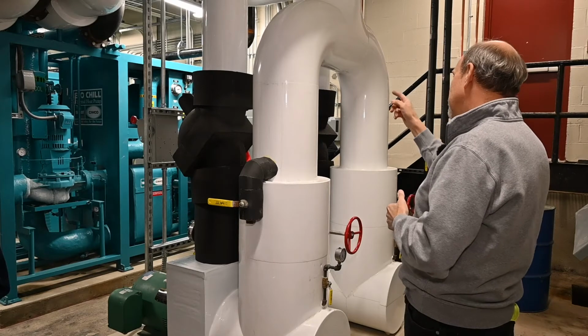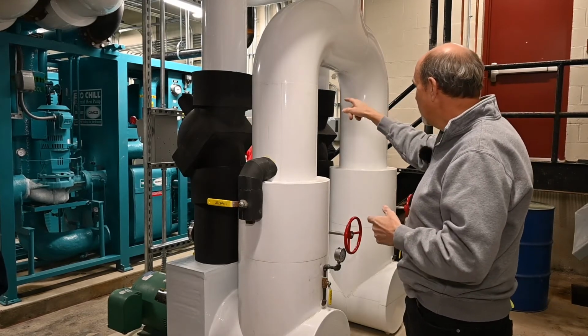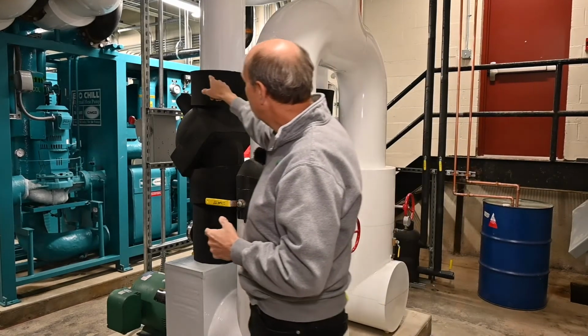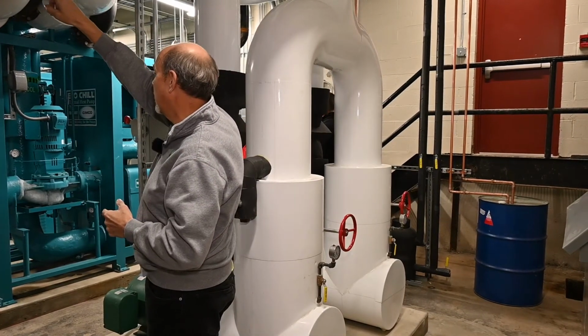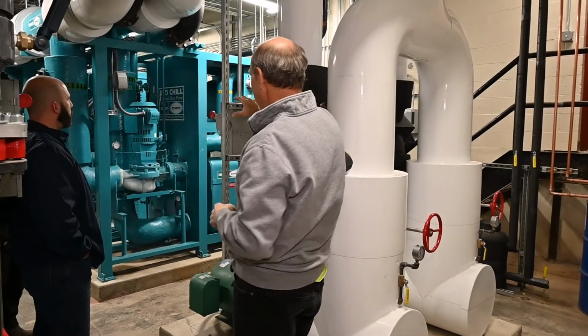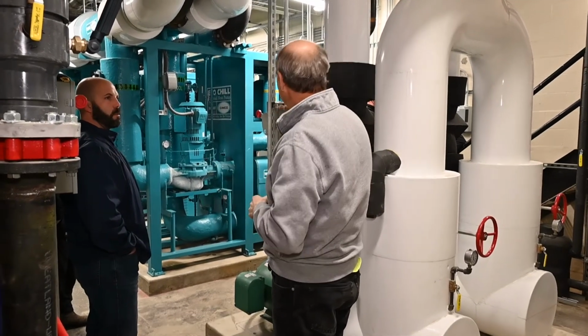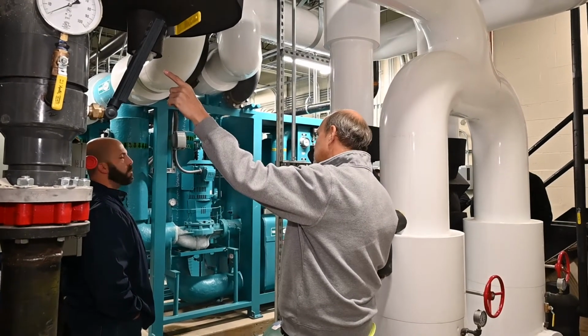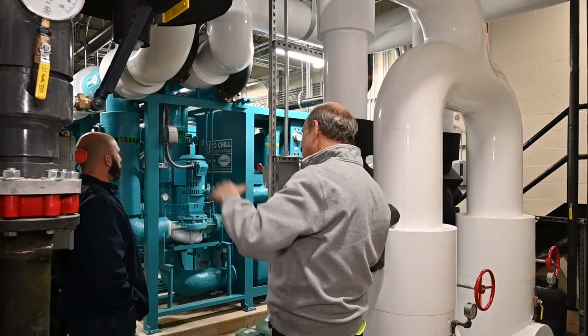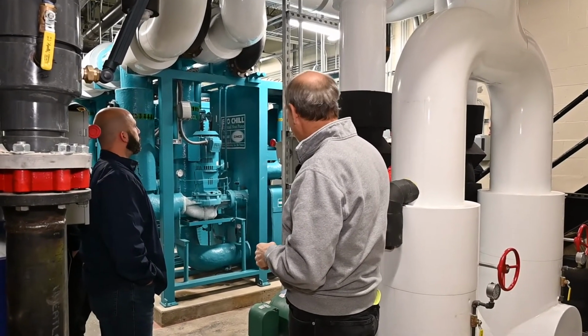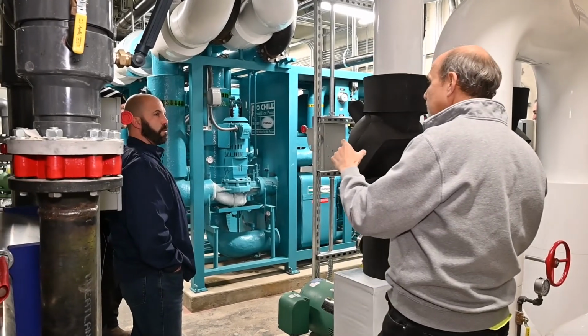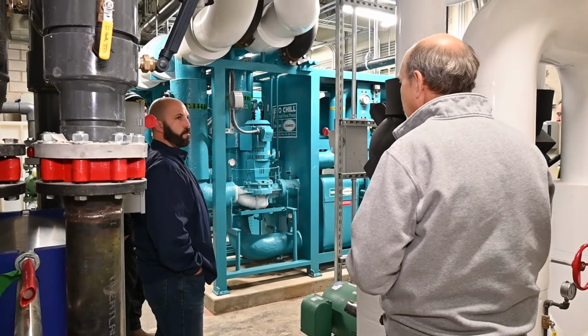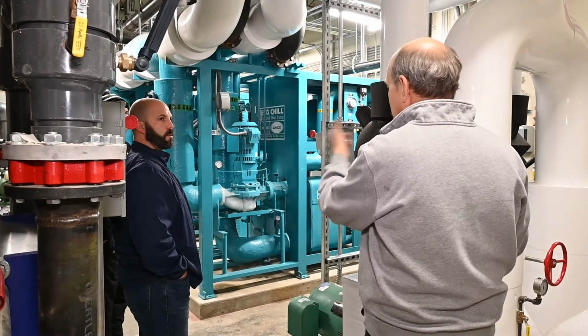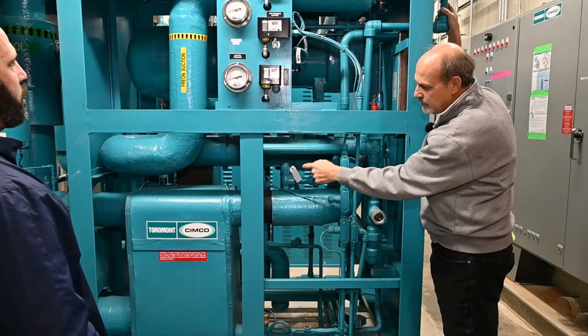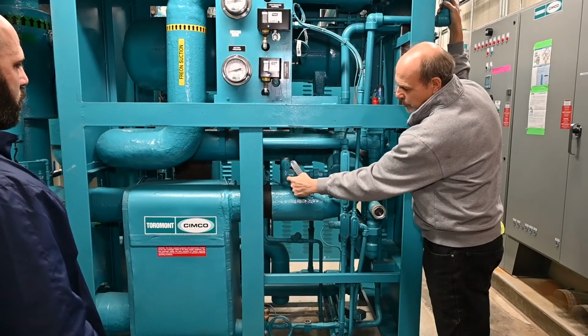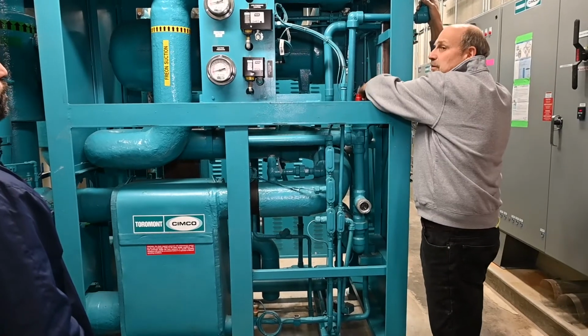The other thing within the chillers, there's relief valves that Kyle can show you, but there's only 2 per chiller, and they go up into this black relief pipe which vents outside. Just like these relief valves that I put in, if the chiller has a malfunction and overpressurizes, that relief valve will dump into that pipe and dump outside, so it gets the refrigerant safely outdoors as opposed to in here. Those relief valves have a tag on them, and those have to be changed every 5 years. So that'll be part of your master plan of doing that. And I know Rico does that, or ARC does that on all the DCR chillers as a maintenance issue. The relief valves I was referring to as far as maintenance, each chiller has 2. There's one here with a tag and one here with a tag.